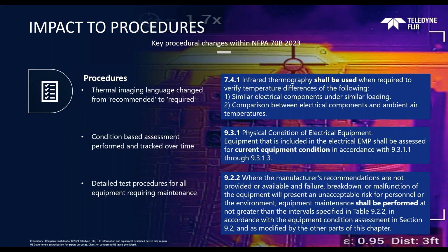It's important to call that out when we talk about proper execution of an electrical inspection. The condition-based assessment performed and tracked over time, this is that physical condition assessment. It needs to be documented in your electrical maintenance program, and established with those various requirements in 9.3.1.1 and 9.3.1.3. If you're feeling like you need to take a nap later this afternoon, I encourage you to pull that document out and have a read. It'll help, but those are the areas with those rules required for compliance, and just understanding what we're talking about when it comes to condition itself.